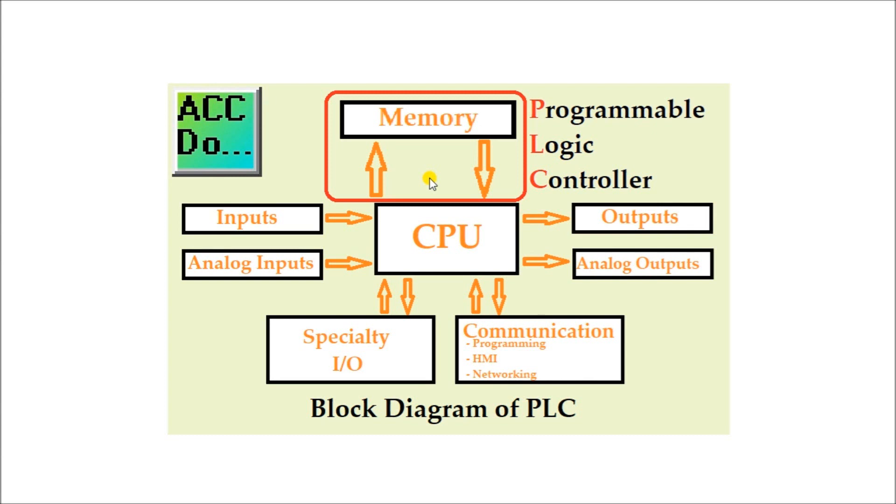PLC program storage and loading. Every PLC manufacturer is different in how they store and use the PLC program and data that you write. Some use flash or SD RAM cards to save the program without a battery. Others will use a battery capacitor or other rechargeable energy storage module to hold the PLC programming data. When the PLC is powered on, usually the program is loaded from non-volatile RAM into the user memory RAM of the controller.